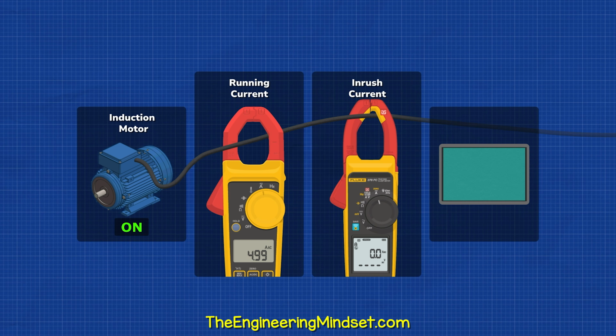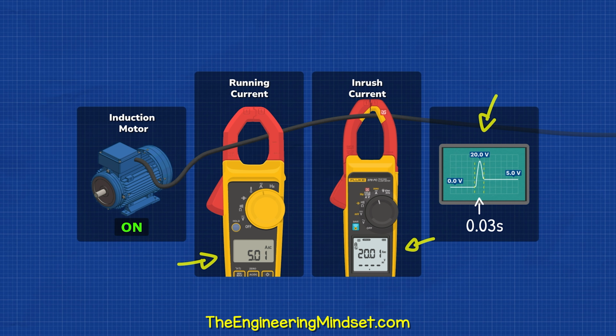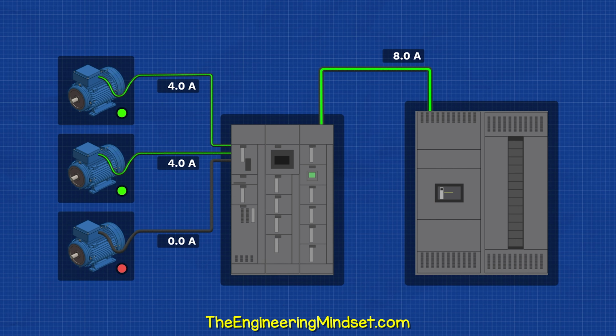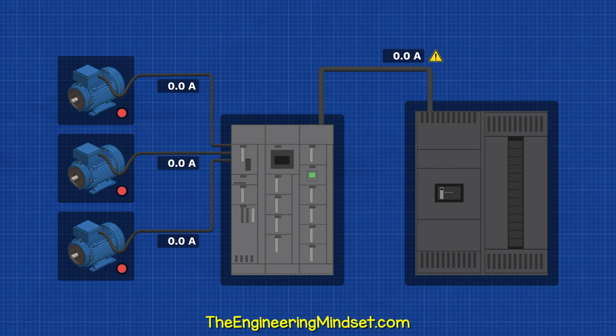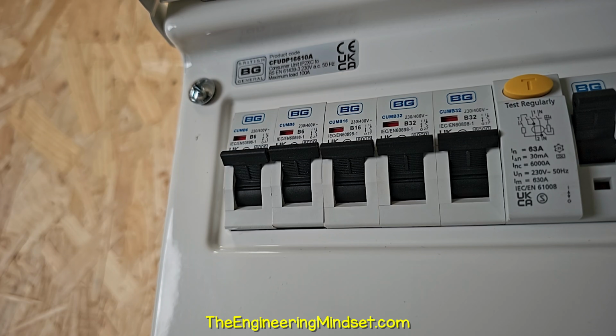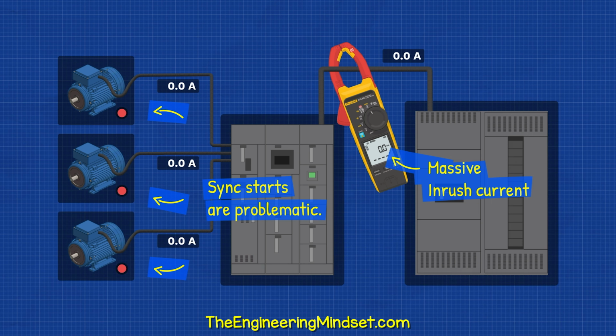Equipment like this induction motor might have a running current of 5 amps, but the inrush current is maybe 4 to 10 times this value. It only lasts maybe 0.03 seconds, but it happens every time the equipment starts. This can be damaging to the building's electrical infrastructure, and it can also cause circuit breakers to trip. So we need to monitor equipment to find the cause.